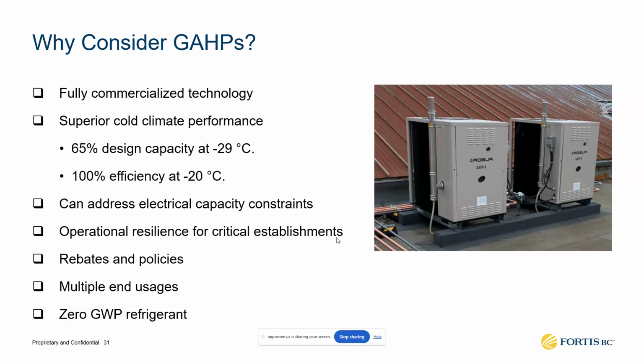Now, in many cases, we've seen our customers installing gas heat pumps just because they have electrical capacity constraints. And in those cases, your gas heat pump will be an excellent application. And in the case of BC, we have rebates, and it's approved under our policies for energy efficiency equipment. And it could be used in any end use that requires hot water. It could be used in heating and domestic hot water, laundry heating, you name it. In any of those applications, it will be a great product for you to consider. Also, as it uses ammonia, it has zero global warming potential. If this is a concern for you, then that will be a good option to consider.